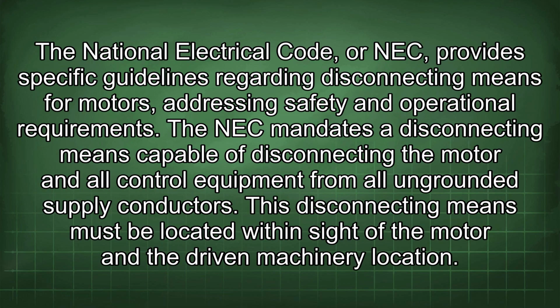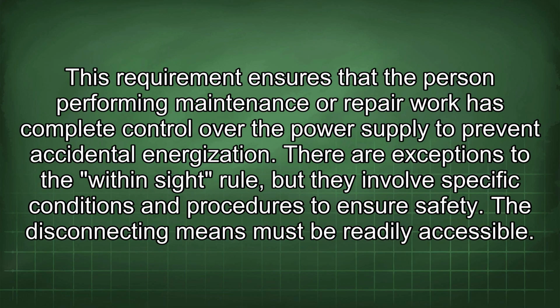The National Electrical Code, or NEC, provides specific guidelines regarding disconnecting means for motors, addressing safety and operational requirements. The NEC mandates a disconnecting means capable of disconnecting the motor and all control equipment from all ungrounded supply conductors. This disconnecting means must be located within sight of the motor and the driven machinery location. This requirement ensures that the person performing maintenance or repair work has complete control over the power supply to prevent accidental energization. There are exceptions to the within-sight rule, but they involve specific conditions and procedures to ensure safety.